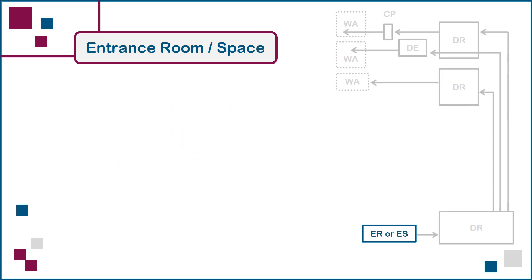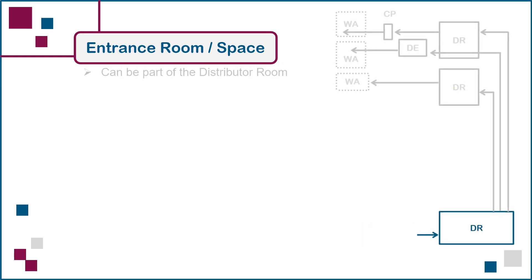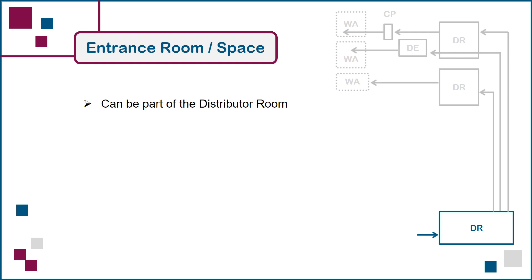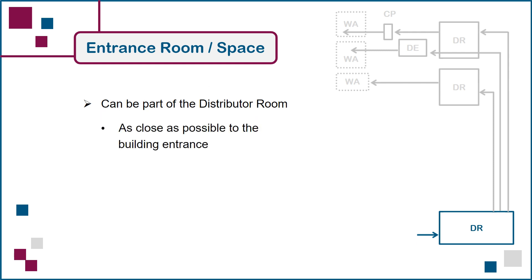It's also possible to eliminate the need for an entrance room or space by terminating the incoming cables in the building's distributor room. In such cases, the distance from the incoming cables' entry point in the wall or floor of the building to its termination point in the distributor room should be as short as possible. This will save space and lower costs, but the designer cannot exceed any length limits on incoming entrance cables imposed by applicable building or electrical codes in the jurisdiction.